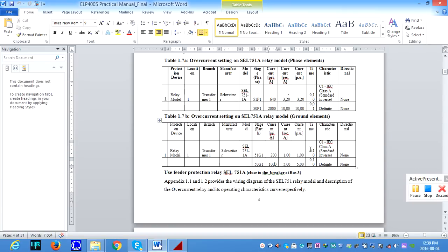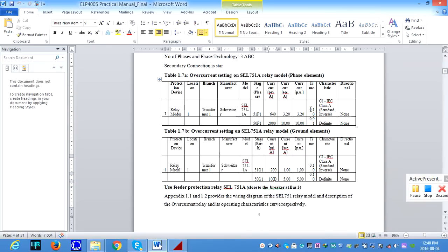And the time you see here for smaller currents is the larger time, 0.10 seconds. For larger current, that is 2000 amperes, you have less time. In this case for ground elements we make the same setting, but for the phase element you can see 0.1 seconds for the 640 amperes. For definite it is going to be 0.01. It's very fast. Okay, this we can validate through the curve. So keep it in mind, 640 to 2000 IEC and 2000 onwards with definite characteristics.